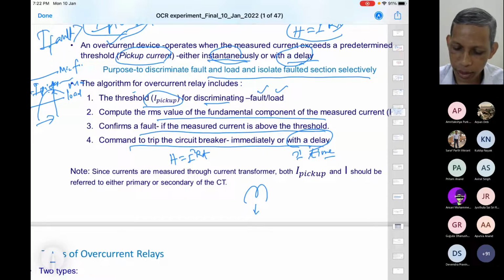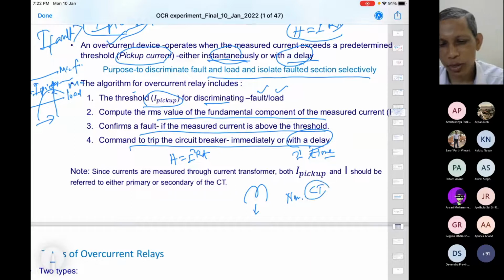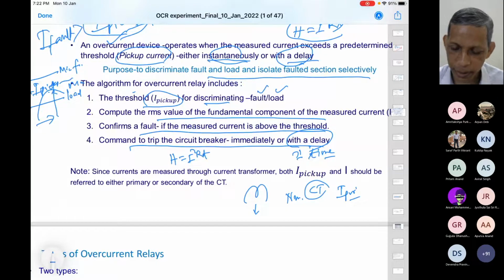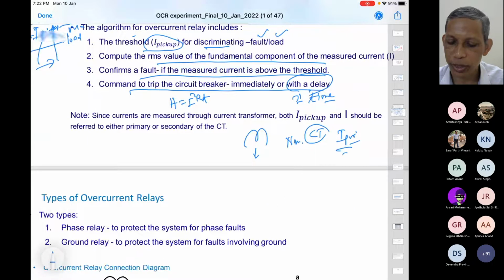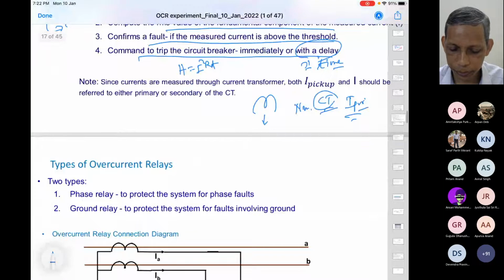But in the case of a numerical relay, you know the CT ratio. So once you have entered the data required for the CT in the numerical relay, the relay can calculate the corresponding primary current. Primary means system side current. That primary, system side current can be used directly by the relay to make a decision about what is happening in the system. It can know in a better way. So we have to enter the corresponding CT ratio for that purpose.